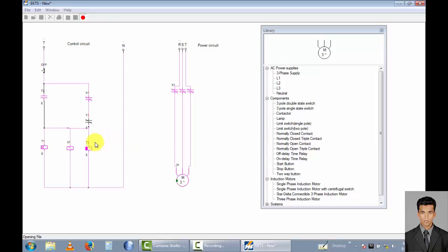Now let's start this motor. After 8 clock pulses or 8 seconds after the motor turns off, and this is an off delay timer, it will become 0 and the motor restarts. Now the motor automatically turns on and off, auto run in forward direction. Off, now off condition, and this is the on condition. 8 seconds after the motor becomes off, and 8 seconds after it becomes on.